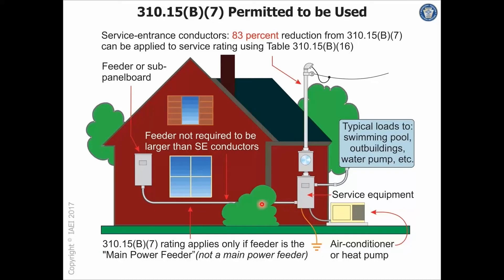In this case, I would not be able to use 310.15(B)(7) on that feeder because that feeder does not provide power to the entire dwelling unit — as you can see, my air conditioner comes off of this panel board back here, and there are also some branch circuits going out to swimming pools, outbuildings, and things like that.